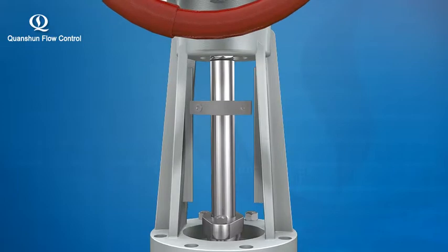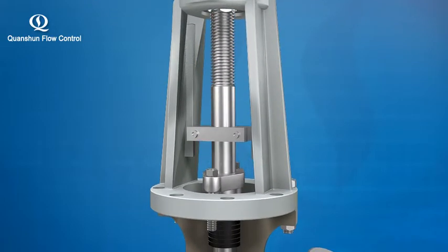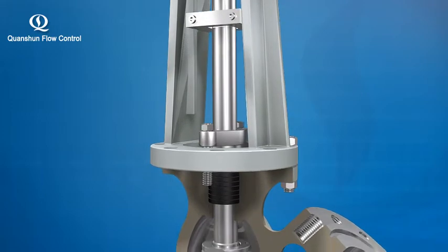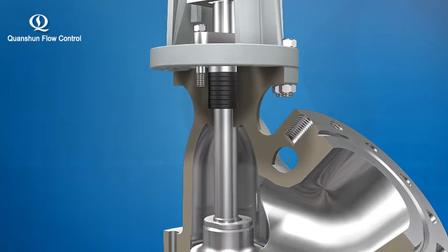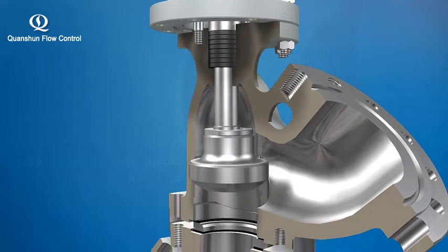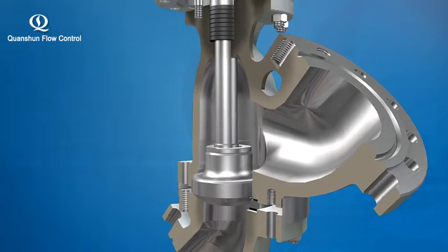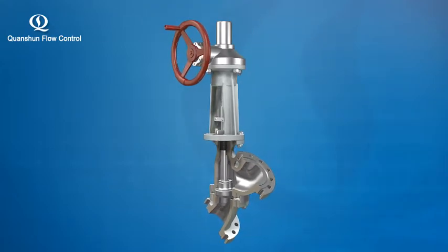5. The use of an anti-rotation mechanism on the stem keeps the stem moving linearly up and down, based upon the fluid characteristics of materials used in alumina plants. The upper flare design ensures the seal face is less likely to be scabbed and guarantees the required seal effect. The special valve design allows the stem to run at no load, even when the valve is scabbed, for the purpose of improving valve operating safety and prolonging its service life.